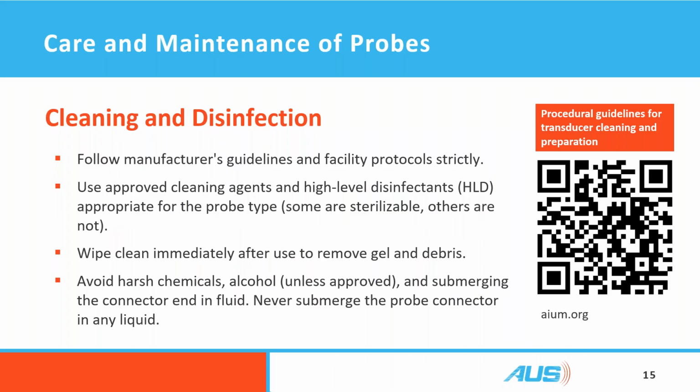You should absolutely wipe them clean immediately after use. You want to remove any gel debris. This is really the sonographer's job, but it's also your job to make sure it's happening, especially if they're accredited through, let's say, American College of Radiology. If they're ACR accredited, one of the things that happens is an inspector comes in and sees gel on a probe while the sonographer is not in the room, and that's considered a patient safety issue, and that can lose their accreditation. So keeping your eyes open for these types of environments is important.